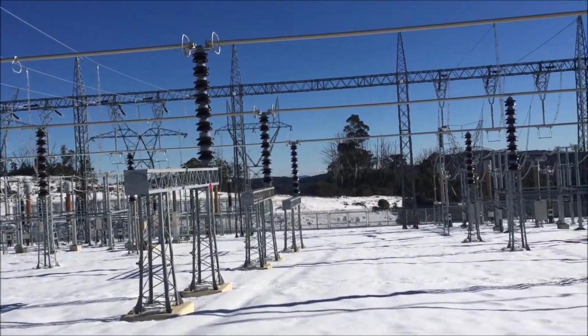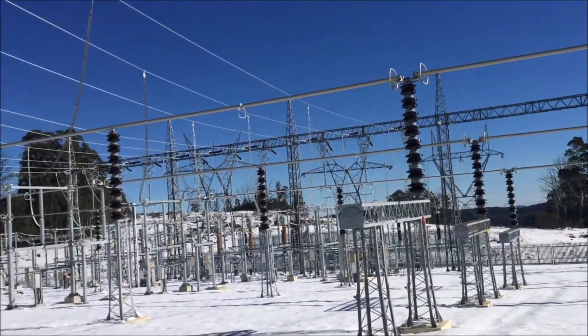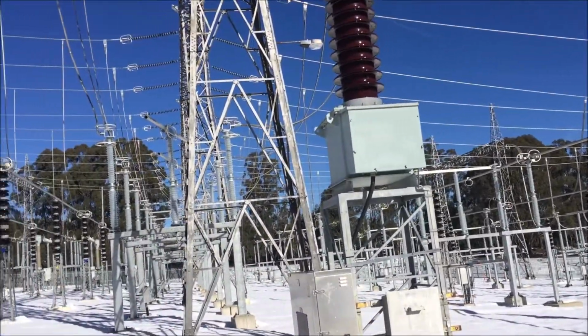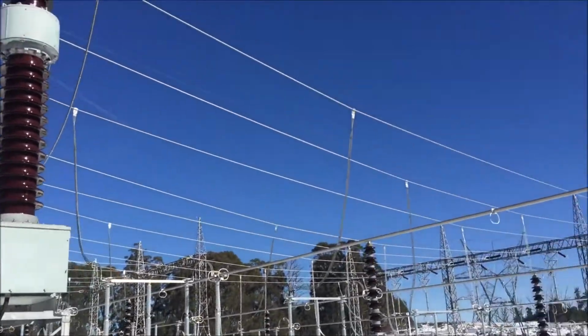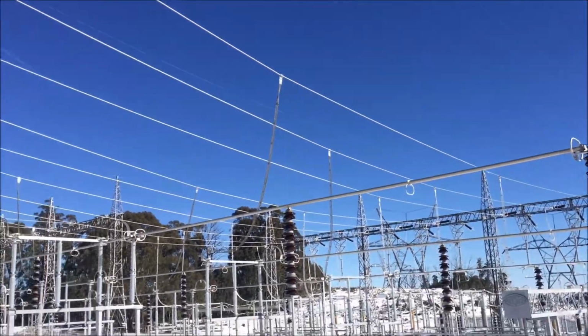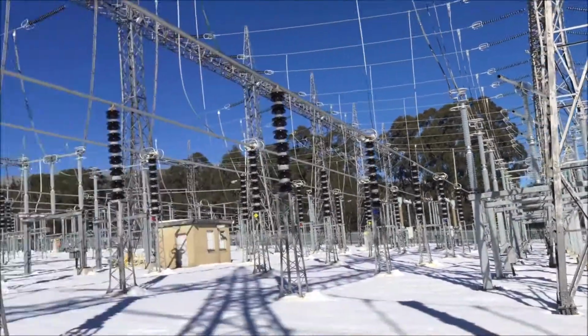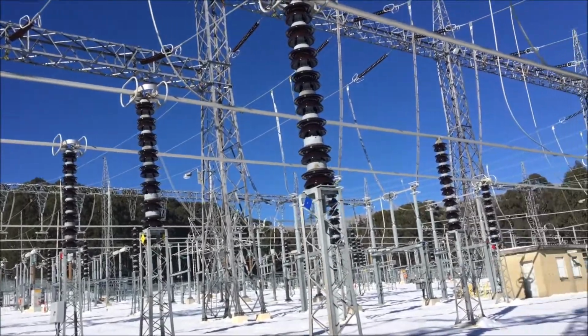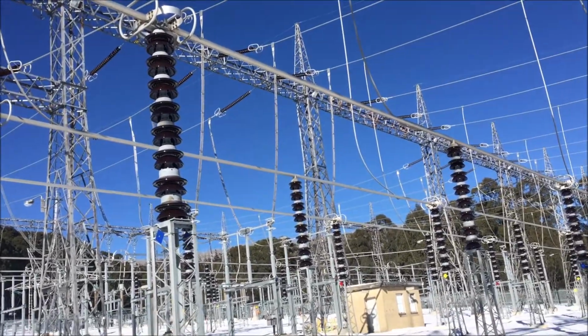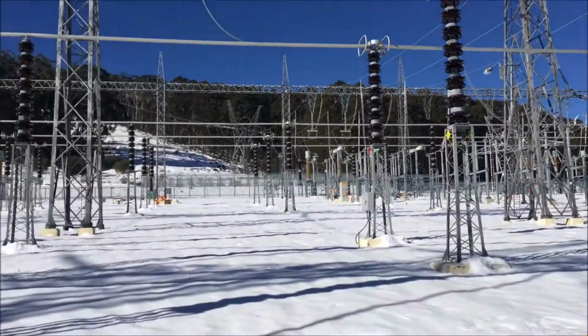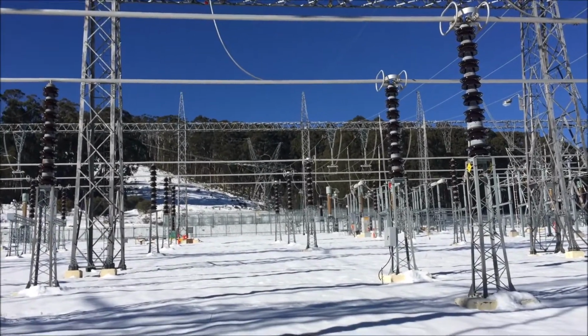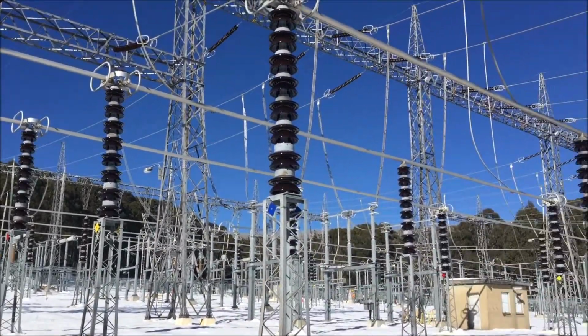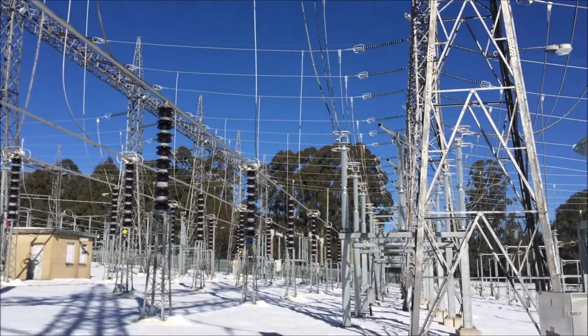So, yeah, the most unusual thing about this place is, of course, it has 3 bus bars. There's an A and B bus, and a reserve bus in the middle. So if you need to get a circuit breaker out for maintenance, you can put the line on the reserve bus, so you're not blacking people out basically.